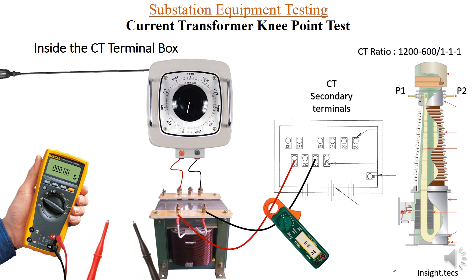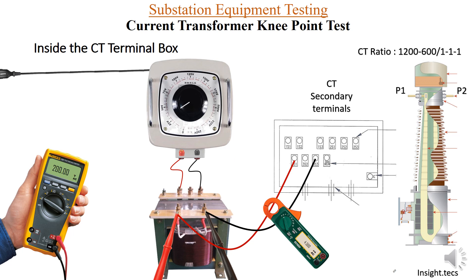Starting the test: at 100 volts, the multimeter reads 100 V and the excitation current is 2.5 milliamperes. At 200 volts, the ammeter shows 4.5 milliamperes. At 300 volts, the ammeter shows 5.7 milliamperes. You can similarly perform this test up to 950 volts, which is the knee point voltage, and also take a reading up to 10% higher voltage.